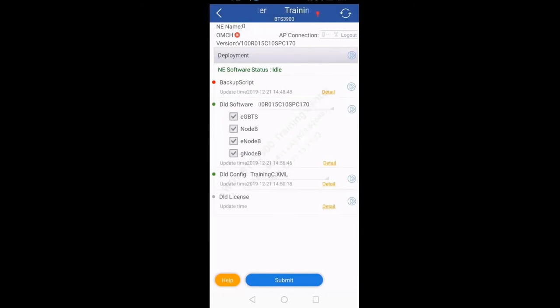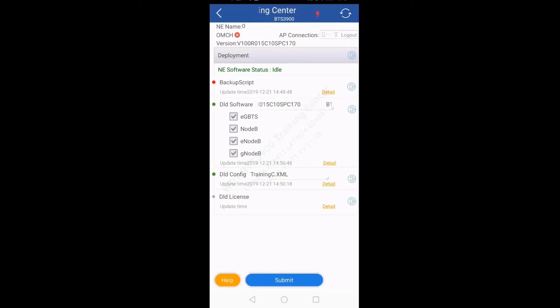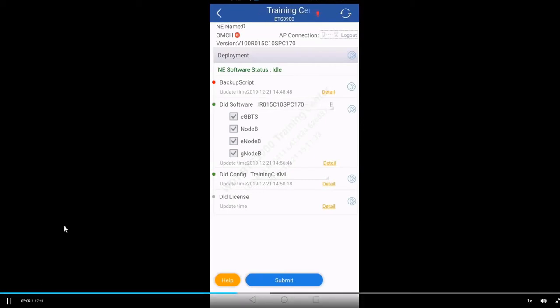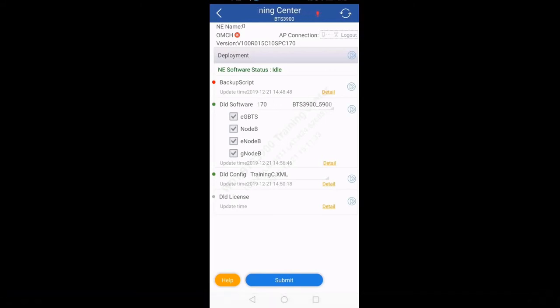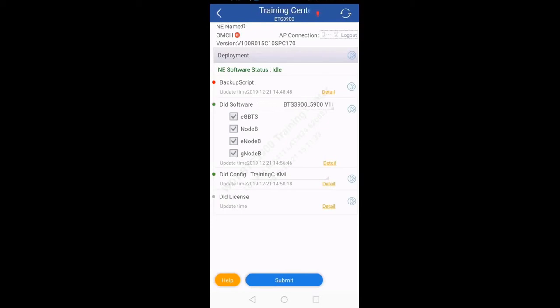Once logged in, at the top left there should be the site ID. OMCH is currently red with a cross because in the training center we don't have any transmission connected to this UMPT, so OMCH is down. But on site this should be green with a tick. Version is showing the software version of this UMPT. If the software version is old, you need to upload the new software version. But if the software version is already upgraded, you don't need to upload any software.